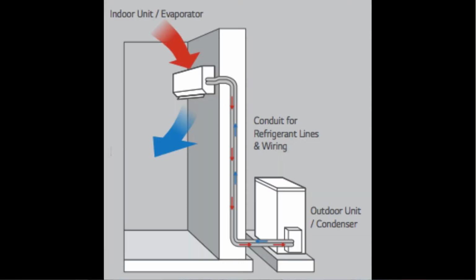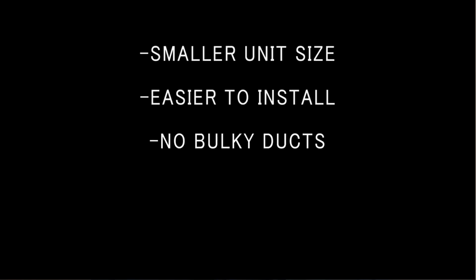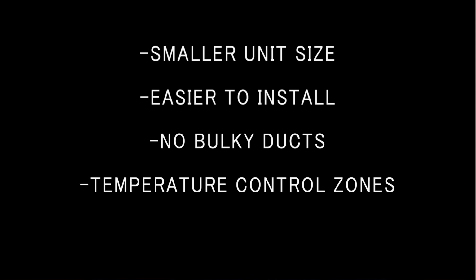There are also some advantages to mini-split systems, such as that they generally have a small size and footprint. Most are under the 400-pound threshold, which means there is no structural engineering design required if it is being mounted on the roof. They are easy to install and have flexibility and convenience when doing so, as you don't have to worry about duct placement, and they can be placed in tight areas between floors and walls, or they can be placed in attic spaces. They also offer flexibility and convenience after installation, as you can use the different temperature zones to keep different people happy in different parts of the space.